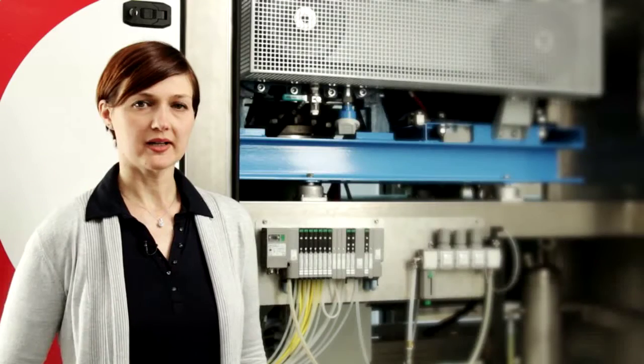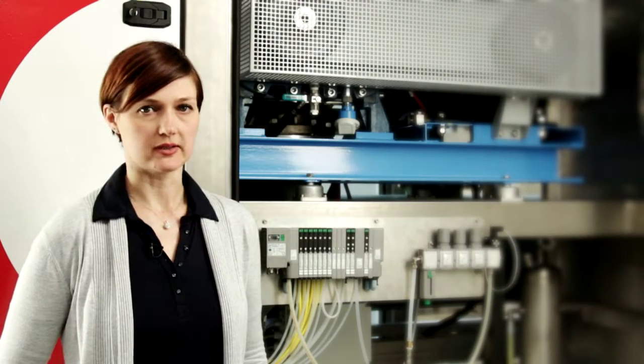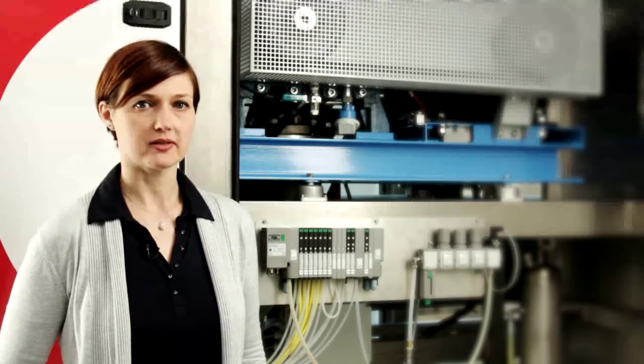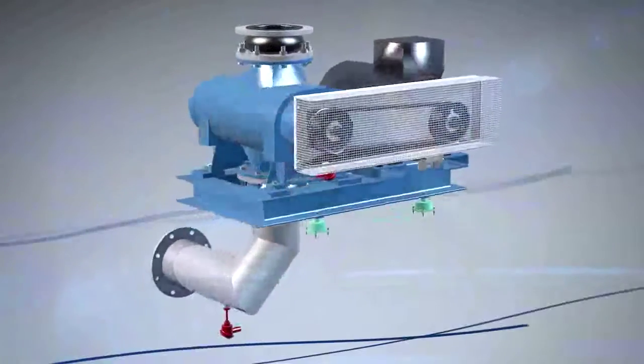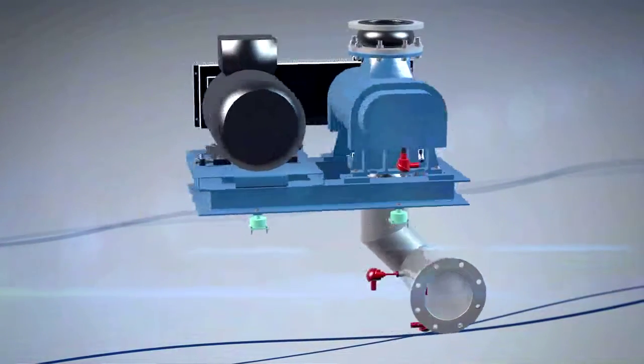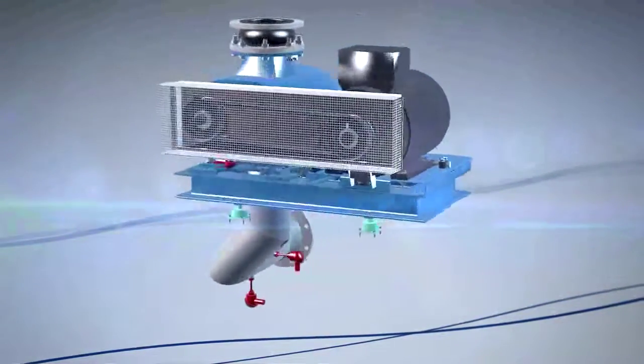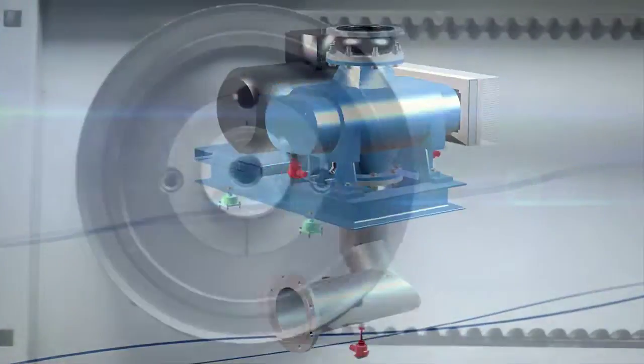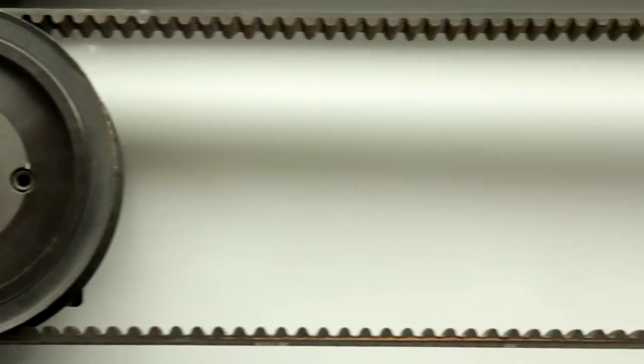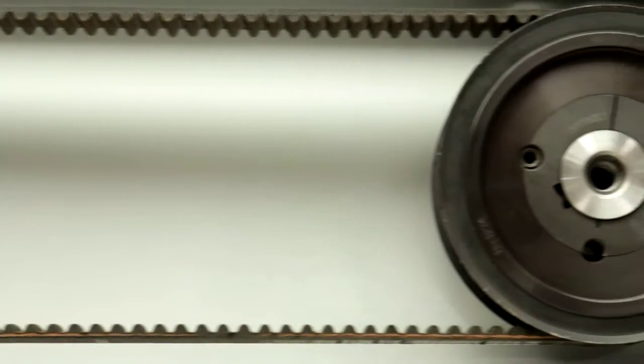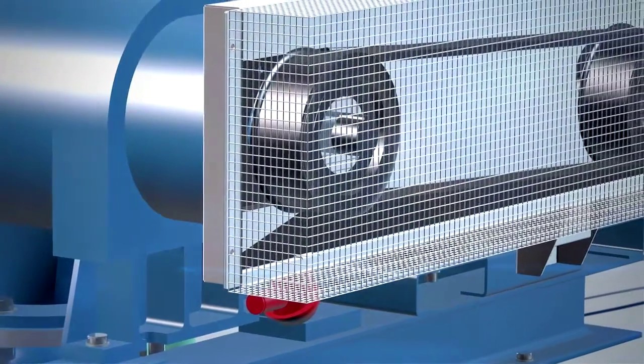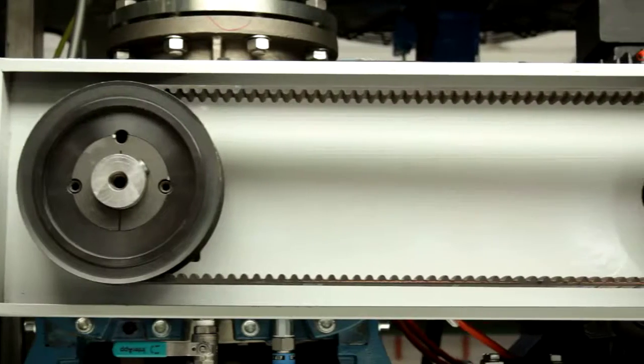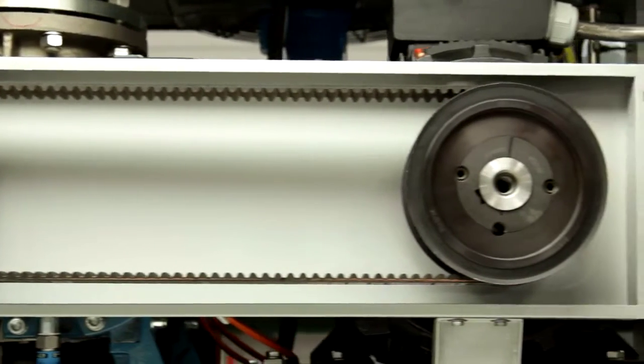Let's continue by looking at the compressor, the core of the unit, as it compresses the vapor to increase the temperature. Its assembly has become easier, as alignment criticalities, typical of direct coupling, have been eliminated, thanks to new generation belts, while its relevant effectiveness in power transmission has been maintained. Furthermore, the compressor is far more resistant to corrosion, as it is made of a particular stainless steel. This means that even the most aggressive wastewater can be treated.